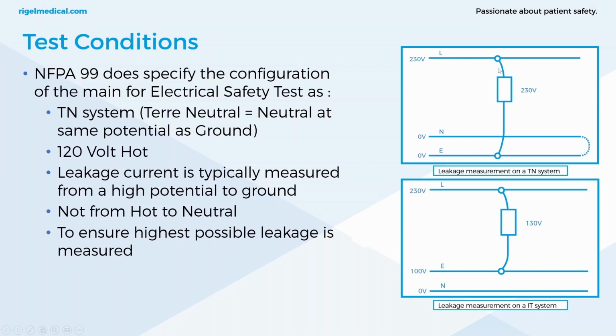I'd ignore the values from this slide. This is from our UK-based presentation. It says 230 volt, so that should be 120 volt, and then we use an arbitrary value for half the line voltage. So 70 volts would be a good example, just to be aware that the values might not be true to the voltages that you're used to.